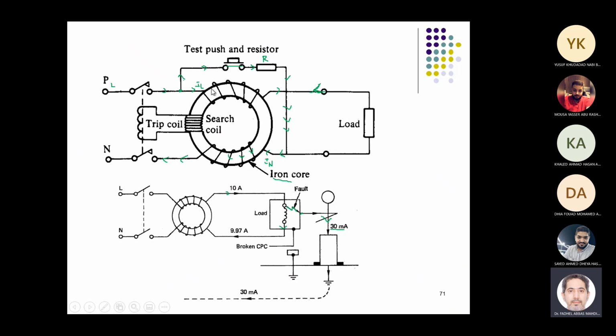So the net flux in the core becomes zero, and there will be no induced EMF in this coil that will trip the breaker. However, when you have a short circuit, like line to neutral, also there will be no net flux and there will be no action. So RCD, residual current devices, does not operate during short circuit or overload or during normal operating conditions.